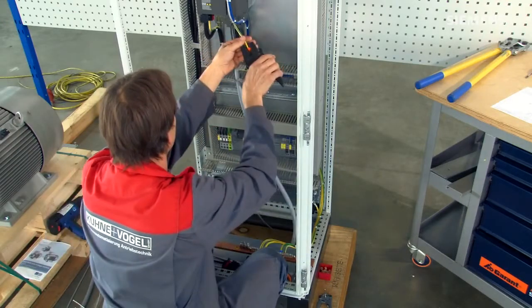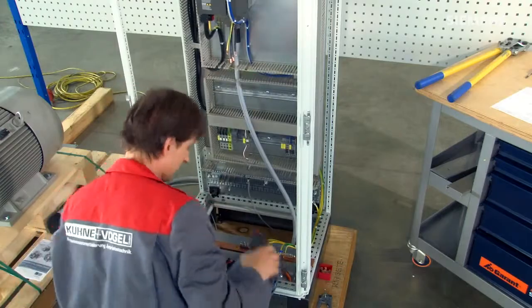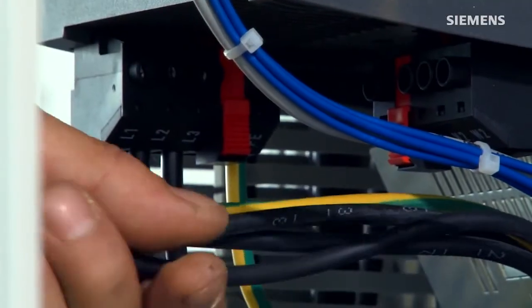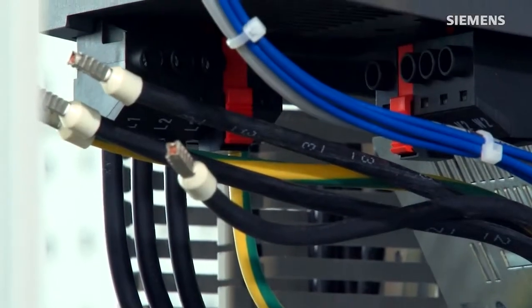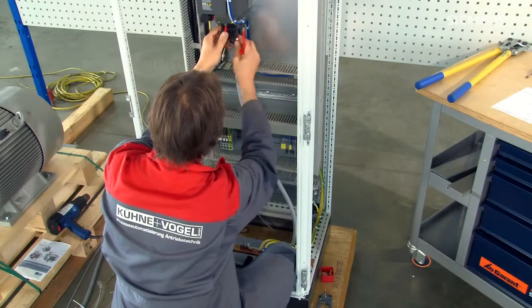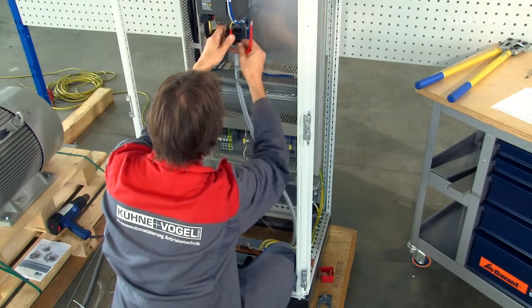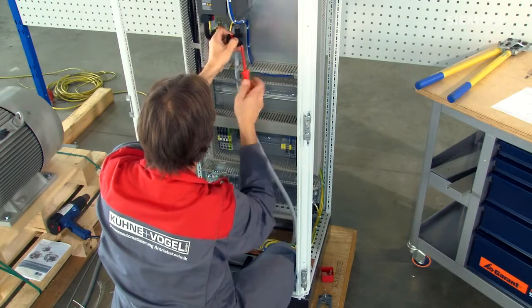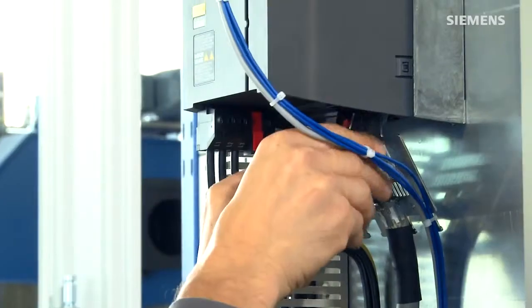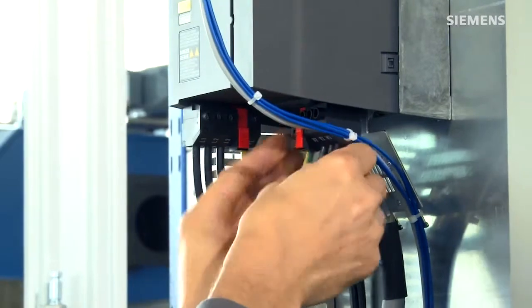Now strip the cable leads and install the wire end terminations. Then clamp the cable leads onto the motor plug and reconnect the plug.